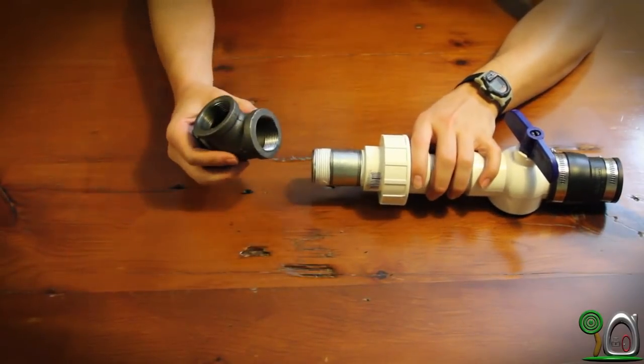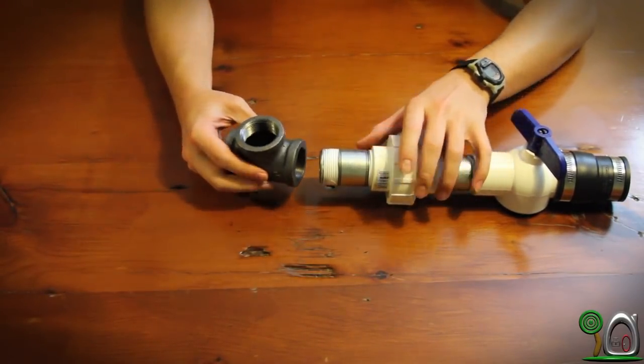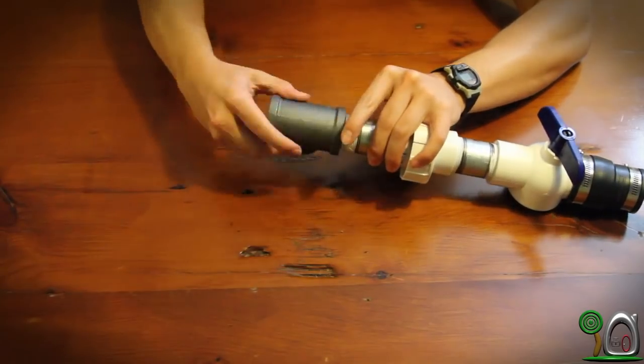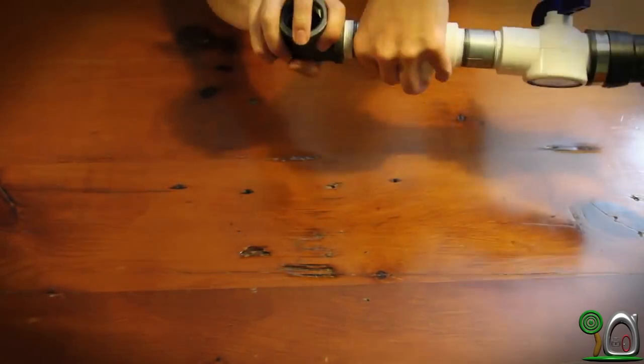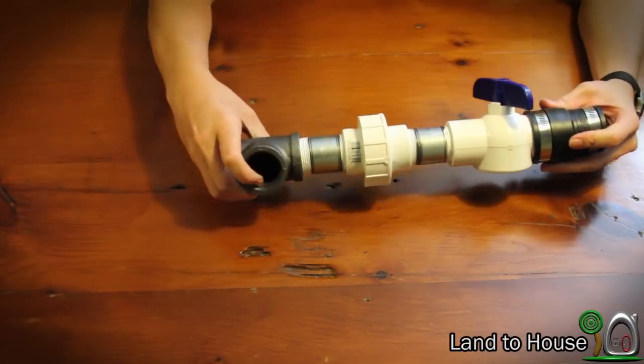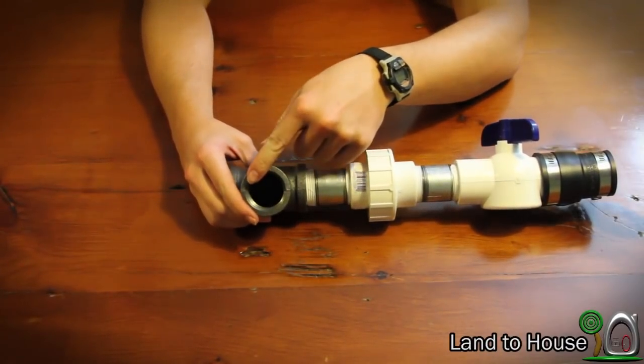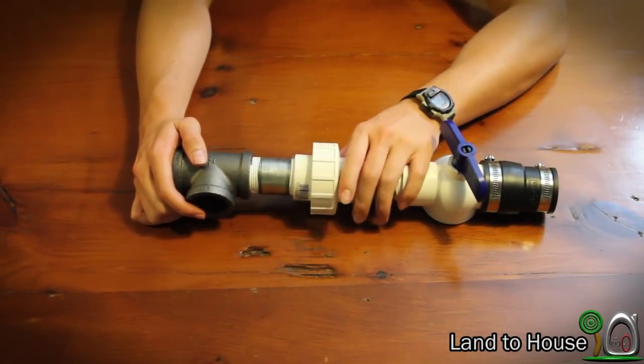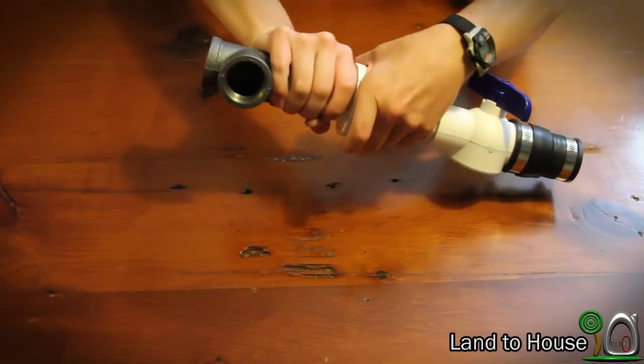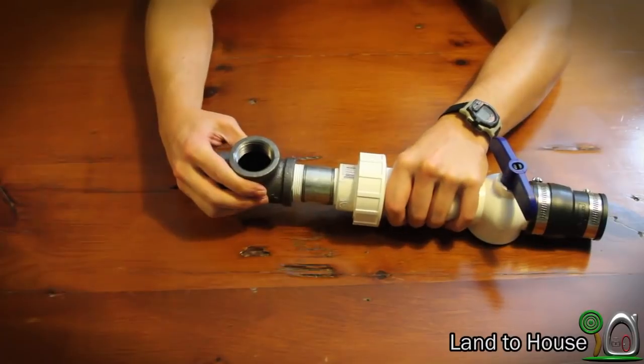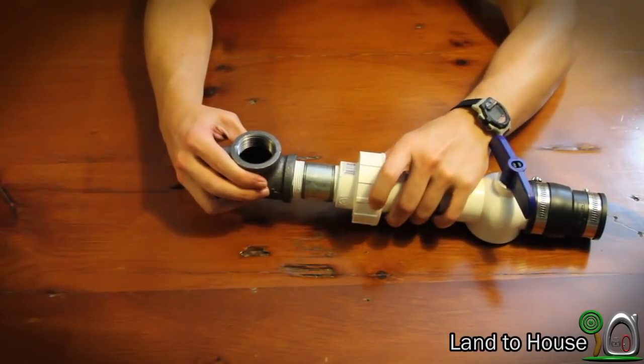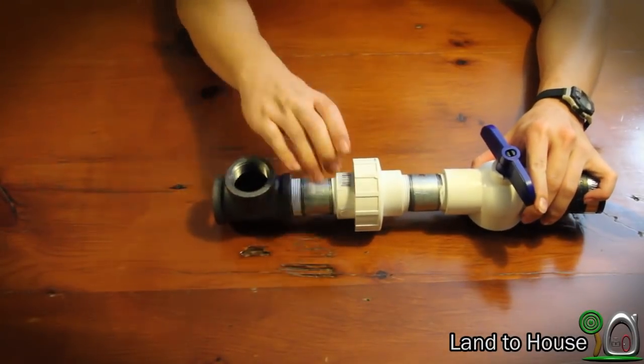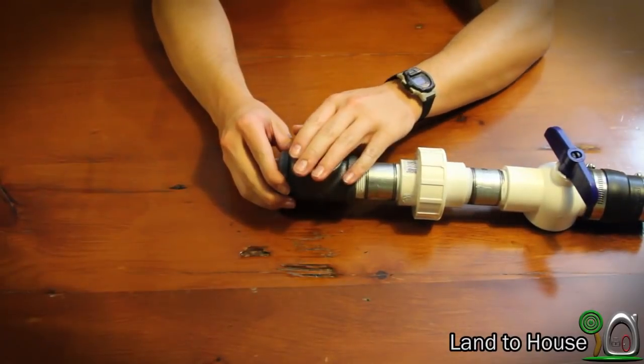Step 6. Take a 1.25 threaded T and screw that onto the pipe nipple. Now you'll notice that this T, when tightened, may not be aligned with the ball valve here. That's where this union comes in handy. You can loosen the union, turn your T to the desired angle, and then tighten your union back down. This allows your T to be facing upwards.